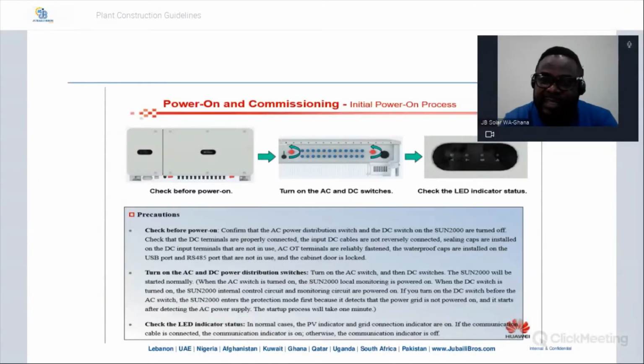If you should change the order, especially between AC and DC, if you put on the DC switch first, before putting on the AC switch, the inverter will give you an error message. And the inverter will shut down to protect itself. You will not be able to power on this inverter until the inverter itself reads that the current in the system is below 0.5 amps. Only after the current goes below 0.5 amps will the inverter allow you to restart the process. So if it's in the afternoon where you have voltages coming from your panels already, it means you are in some sort of trouble. You have to wait until night for the whole amperage of the panels at the top to go below 0.5 before you can redo your system.